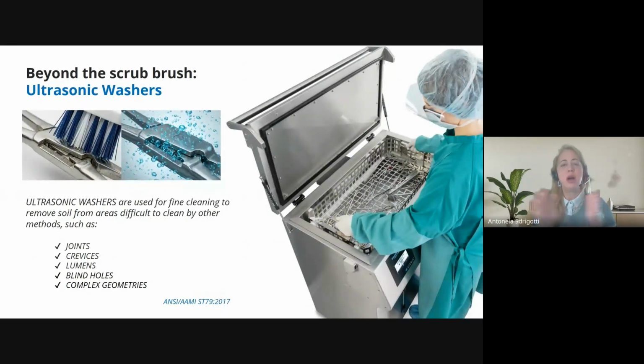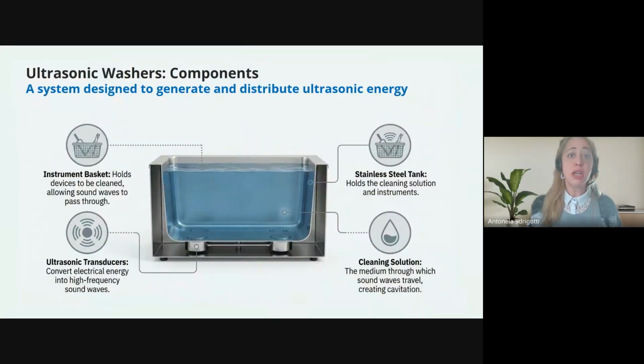Okay, so we have nowadays a lot of different configurations of ultrasonic washers, so it makes it even more important to be sure or to be certain that the cavitation energy delivered within the full tank of the ultrasonic washer is actually working at the right level to clean our medical devices. So, which are the components?